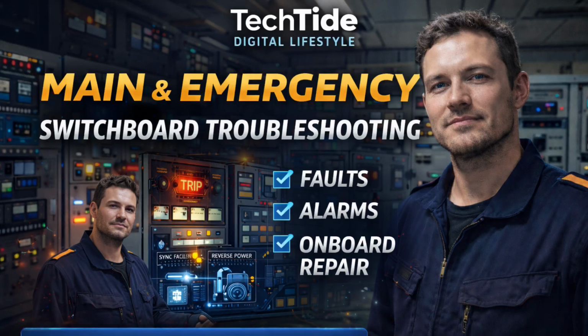In this lecture, we are going to discuss one of the most important practical topics for every marine engineer and ETO: main and emergency switchboard troubleshooting. As you can see on the screen, the main switchboard is the heart of the ship's electrical system. All generators, bus bars, protection systems, and distribution feeders are connected here. When any fault occurs in this area, it directly affects the entire ship. Troubleshooting is not just about pressing reset. It is about understanding alarms, reading indications, and thinking logically before taking action. In this video, I will explain common faults like breaker not closing, load imbalance, overcurrent trips, voltage instability, and emergency switchboard problems, step by step in a practical way. If you are a marine engineer, ETO, or electrical professional, this knowledge is very important for your onboard confidence and oral exams.